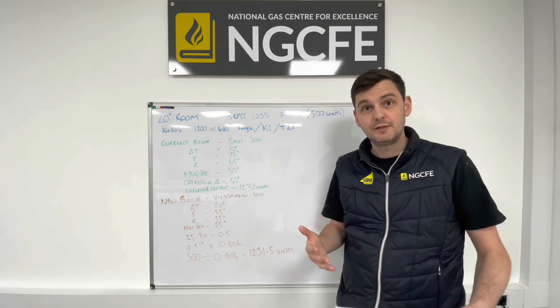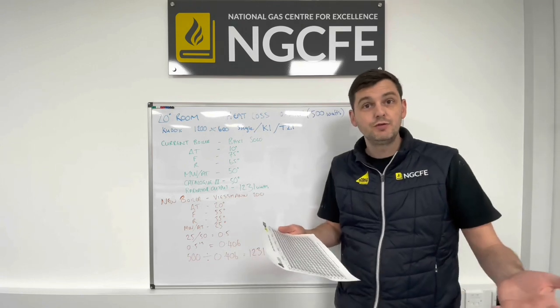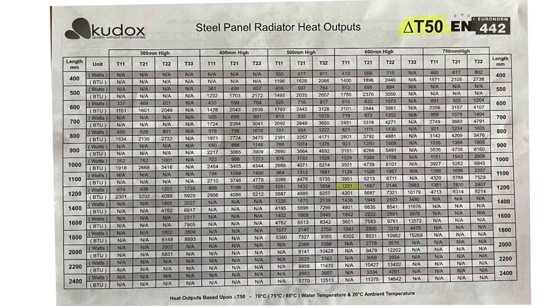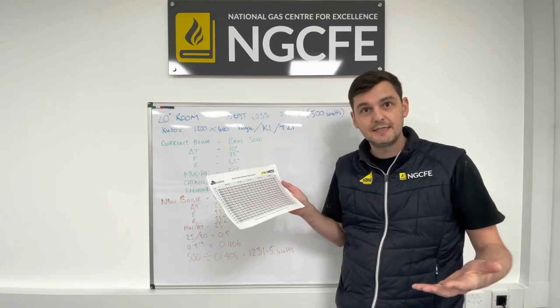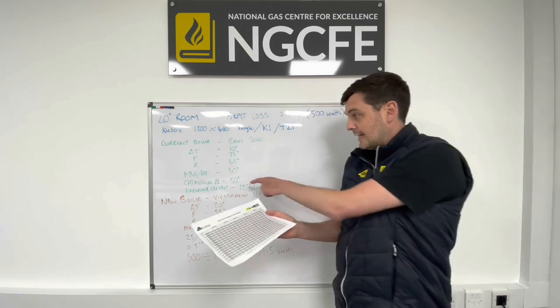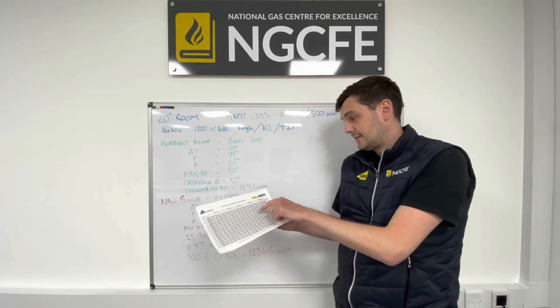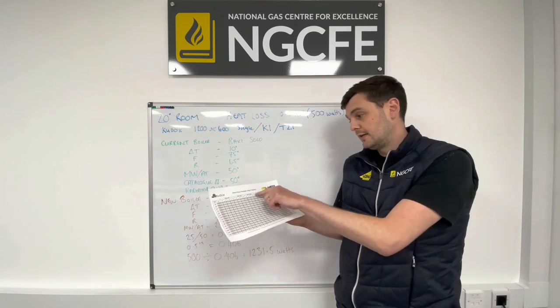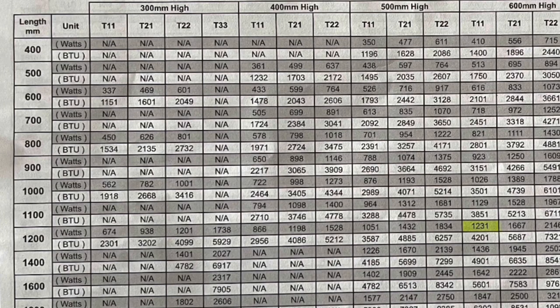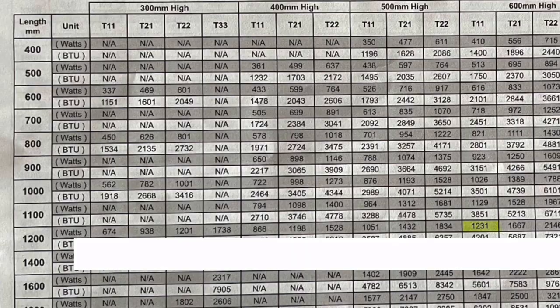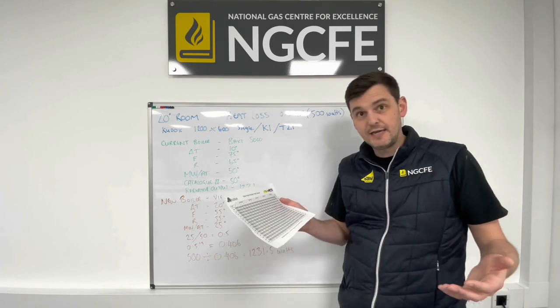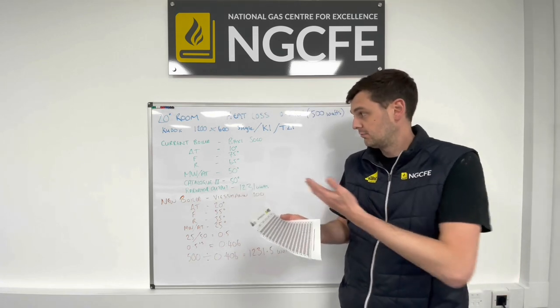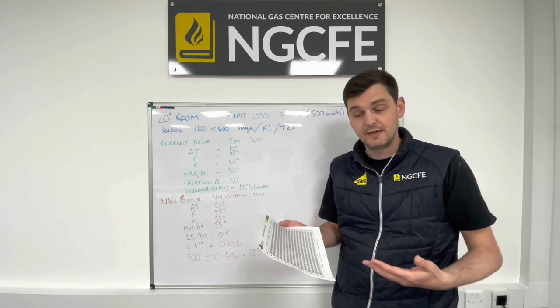It's a Kudox radiator — what Screwfix provides — and I've got the output chart for Kudox radiators here. At a catalogue DT of 50 — flow 70, room 20 — a 1200 by 600 Type 11 radiator gives 1231 watts. That's 1231 watts of heat output into the room every second it's in operation, with a flow of 75 and return of 65 from this existing non-condensing Baxi Solo with a DT of 10.